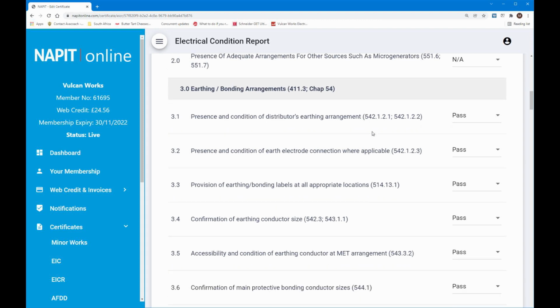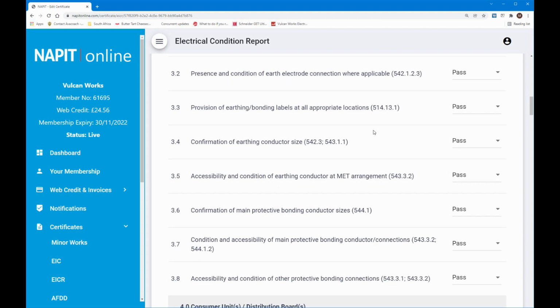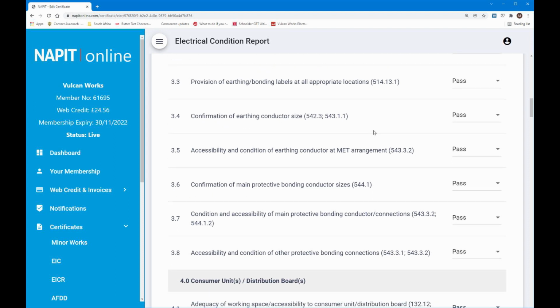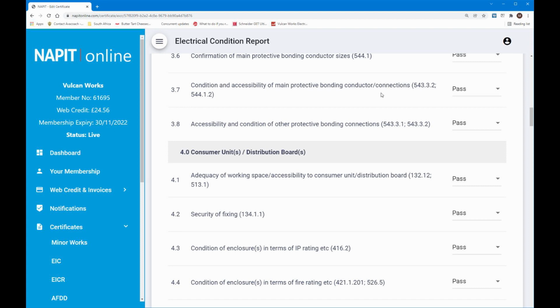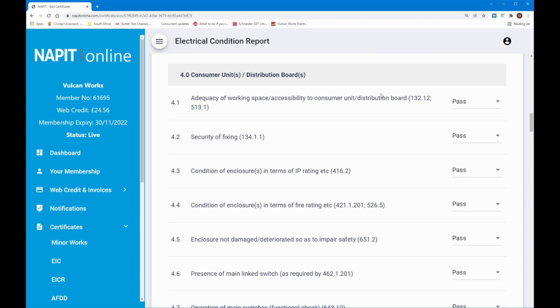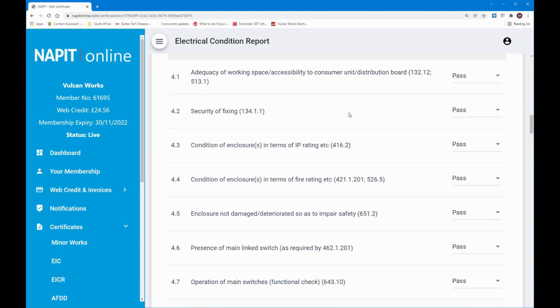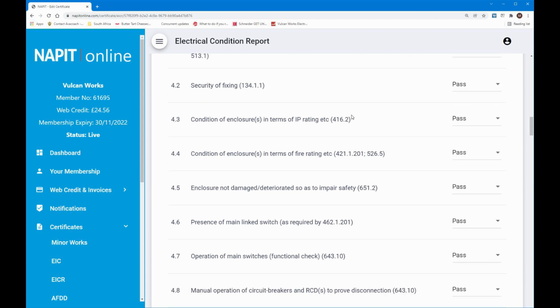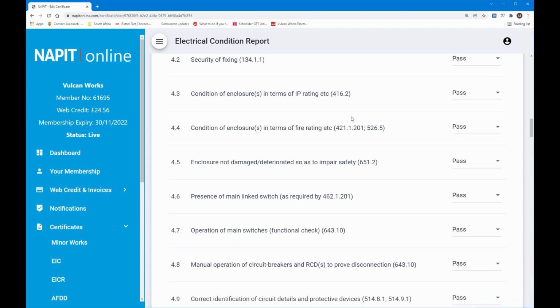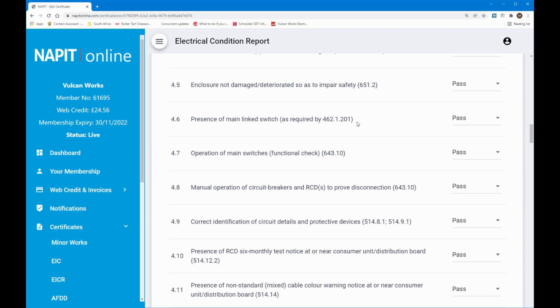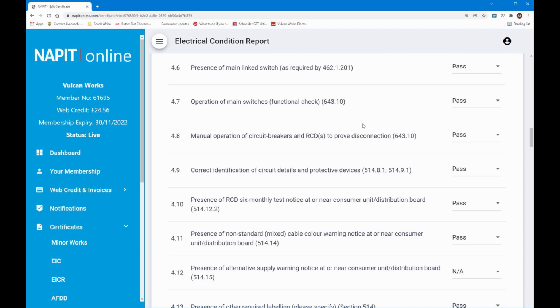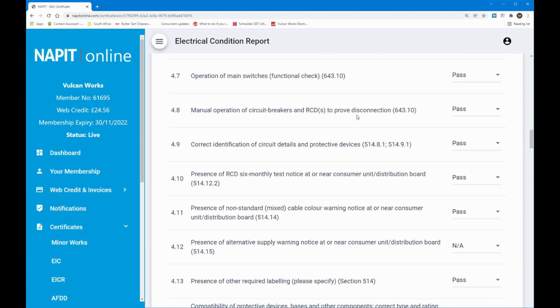Earthing and bonding, I believe all passed. If you go all the way down through here, there's a lot to do. That was all fine. There was nothing wrong with the earthing that I found. Now the consumer units, this is where we have got an issue. Adequacy of working space, that was fine. Security of the fixings, fine. IP rating was fine. The fire rating is currently fine, it's actually a metal enclosure. It's not damaged. There is a main switch. The main switch works. The RCDs, yes, I did do the test button and everything else, but you'll see those in the results. That's all fine.